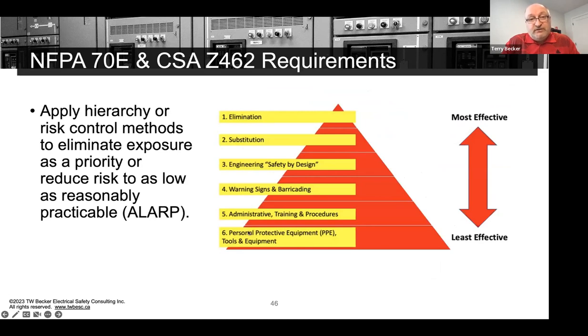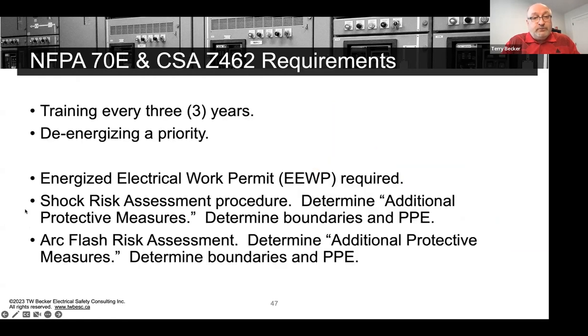This is the 6 hierarchy of risk controls. Elimination is the first one. Substitution and engineering safety by design really have to be completed by the electrical equipment owner, right? Or the company that specifies that electrical equipment. Warning signs and barricading, applying training and using procedures to achieve residual risk level reduction. And then the PPE is last, all right? So 6 controls, and we want risk as low as reasonably practicable.